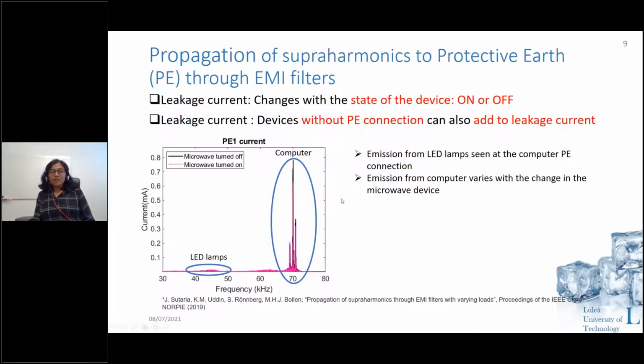Also, some devices don't have their own PE connection, such as LED lamps, which are usually very small and usually have very small supraharmonic emission. But even that emission, if it ends up in the leakage current, is going to increase the leakage current value.